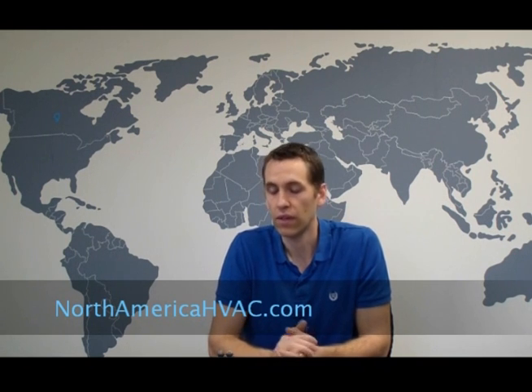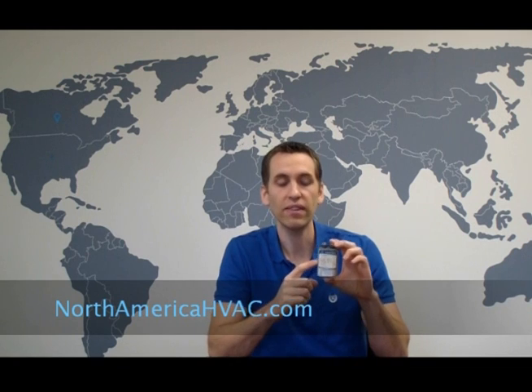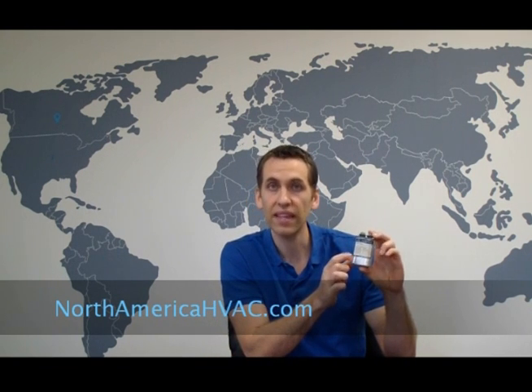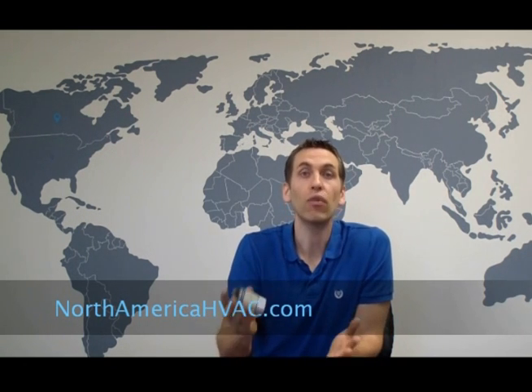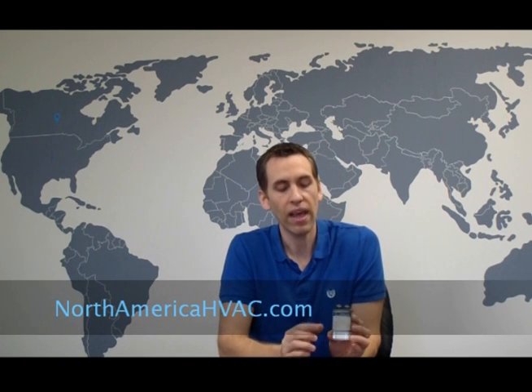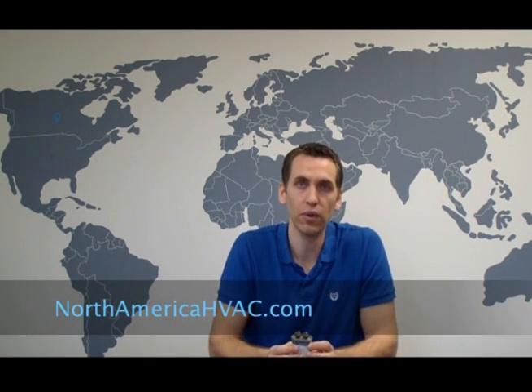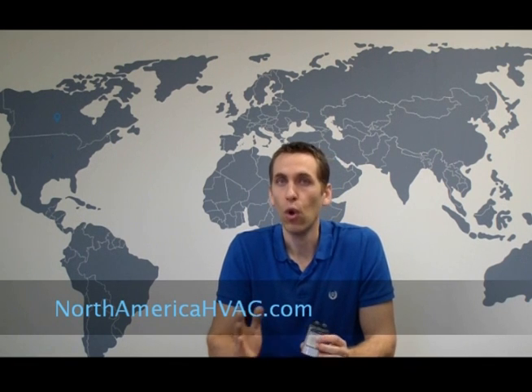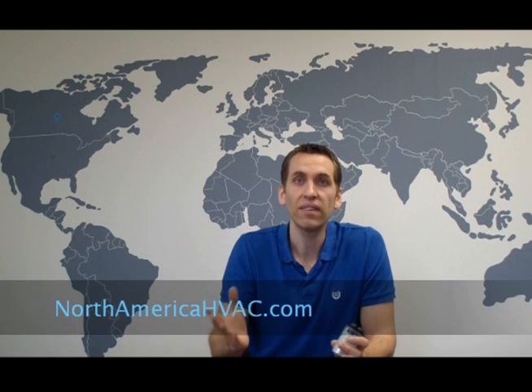The thing to consider is that as you increase the voltage rating of your capacitor, you're increasing the amount of dielectric fluid inside it. If you double the voltage rating, you double the dielectric fluid — that would be a great capacitor. But you also need a canister that can contain double the dielectric fluid, which means the old capacitor and the one you order may have a slightly different size.